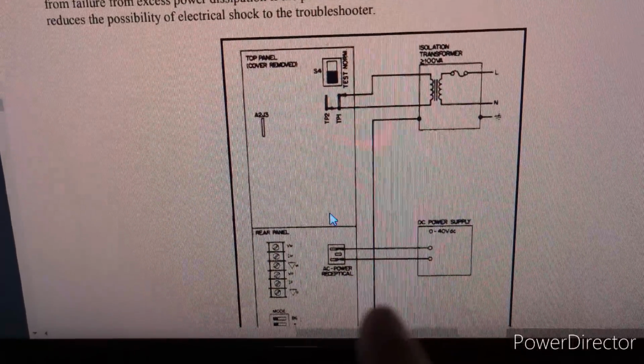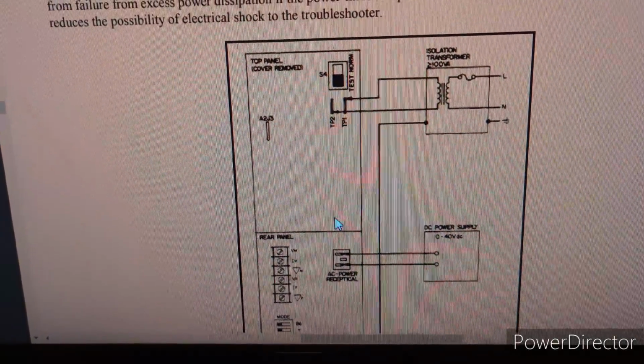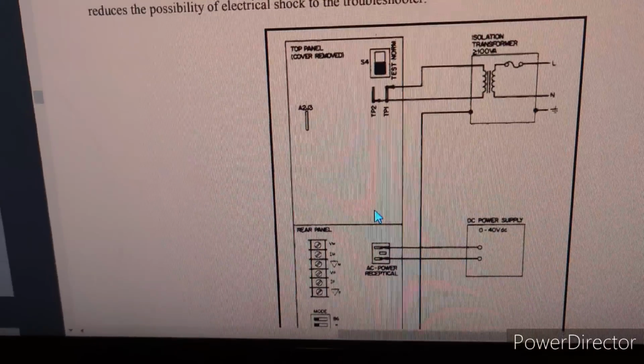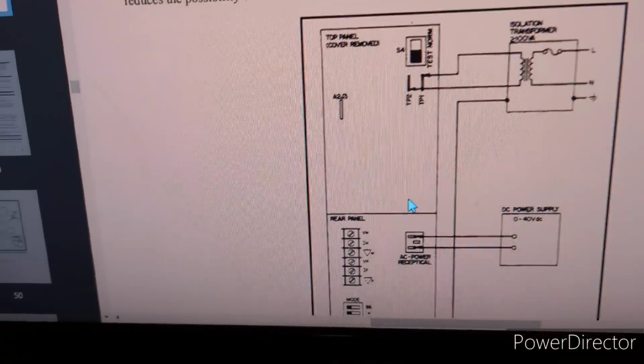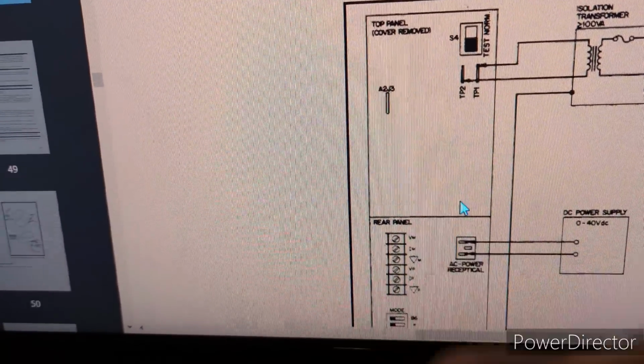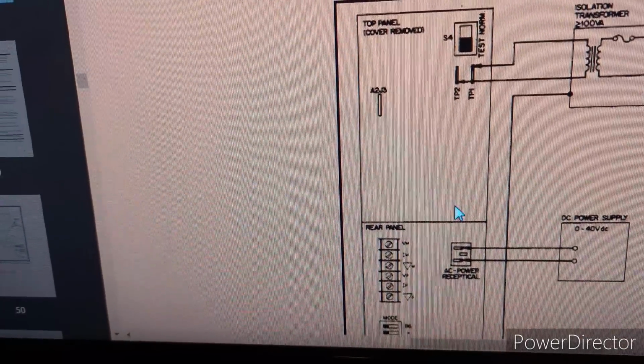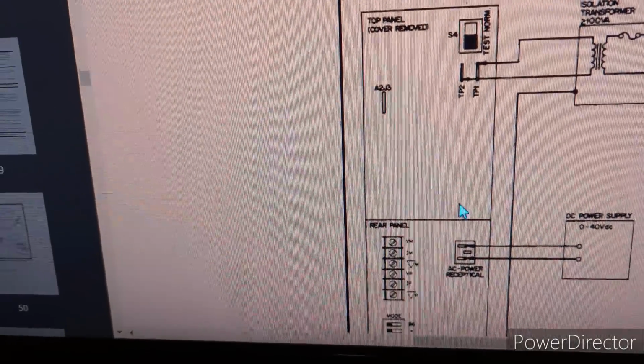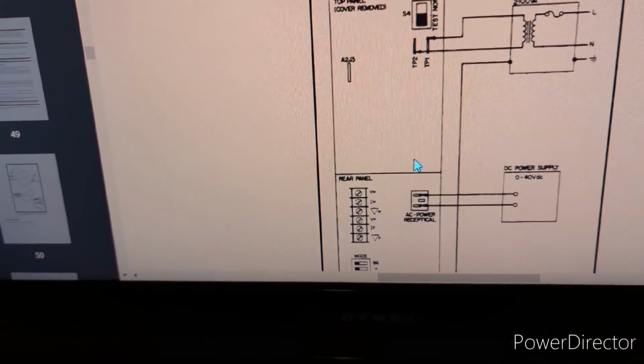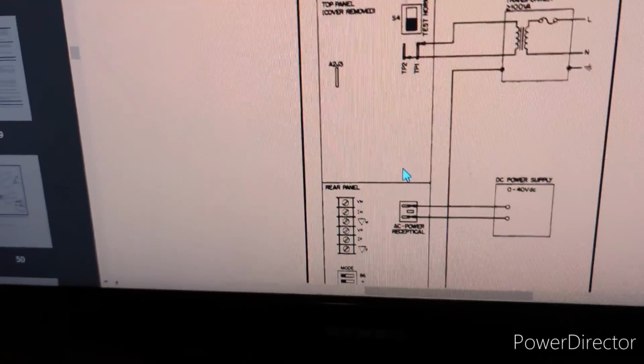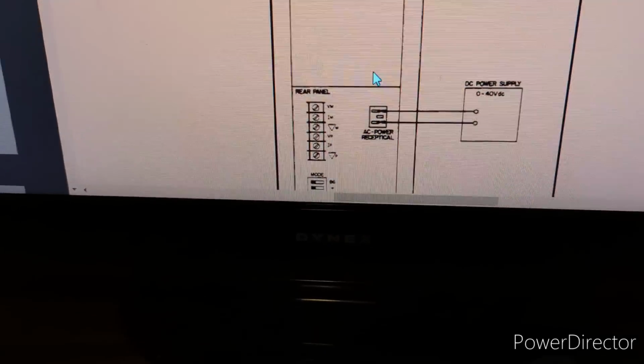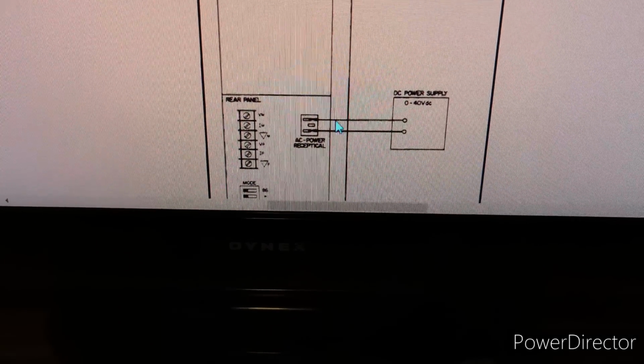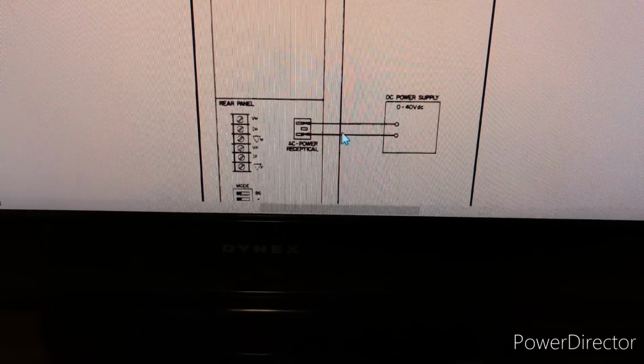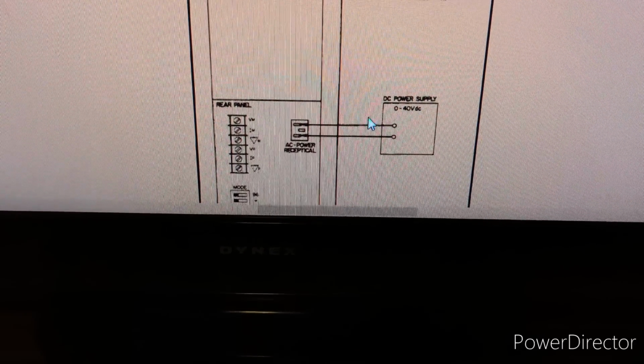There's also a switch by those test points that you can switch from normal operation mode to test mode, so that switch is put into test mode. This connector, A2, J3, so A2 is the control board, and J3 is the connector where we are going to be doing most of the probing for test points. And then down here, on the power receptacle, they've got a DC power supply hooked up to it.